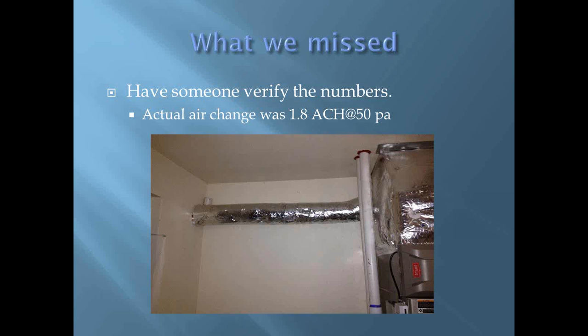And in a hurry to try and meet the new codes, I drafted an amendment that was passed that says this is an acceptable method for dealing with your ventilation air in new houses versus trying to do exhaust fans, and I don't really want to get into all of that. But it's in there now as an option for doing your ventilation in new houses. It's 20 square inches per 1,000 square feet is what it calculates out to. And I tested it under all the different scenarios. The beauty of doing things on your own house is you can go out there and test it.